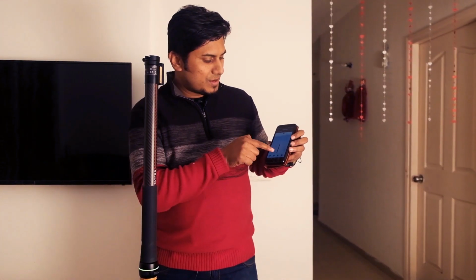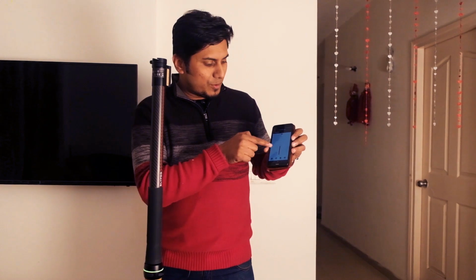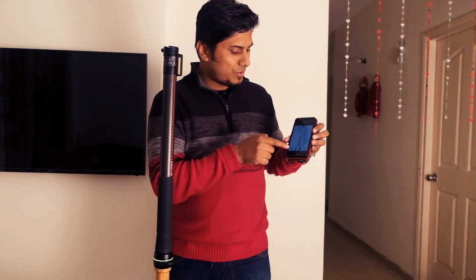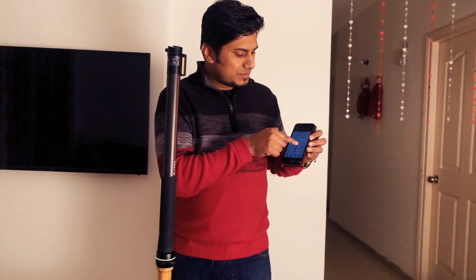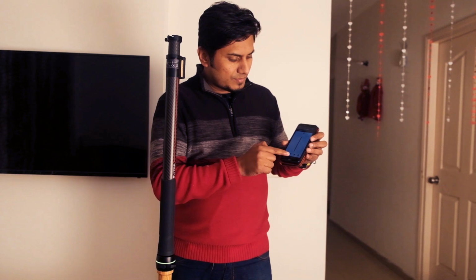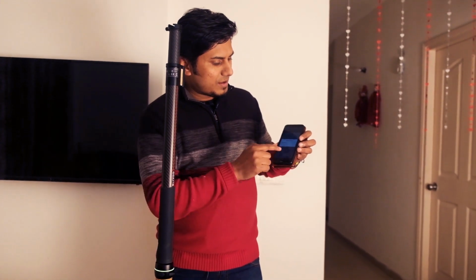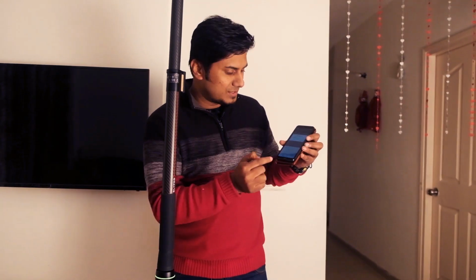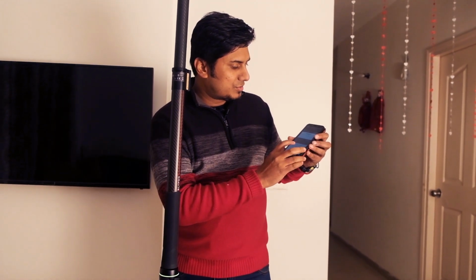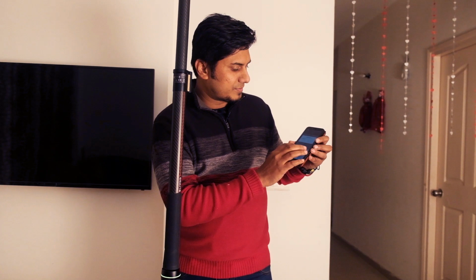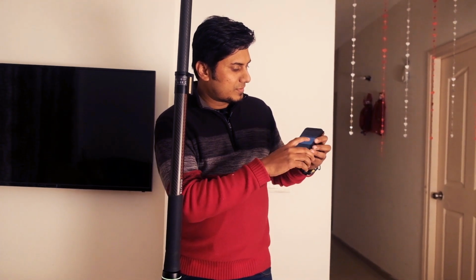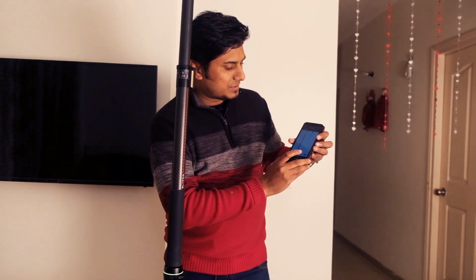In segmentation mode, there is a start point and an end point. You can give different paths, as much as 5 different paths of movement. You set the start and end point, confirm, and it will ask for how many seconds. It was 14 seconds here; we will make it 20 seconds and confirm. After confirming, you can add a path.